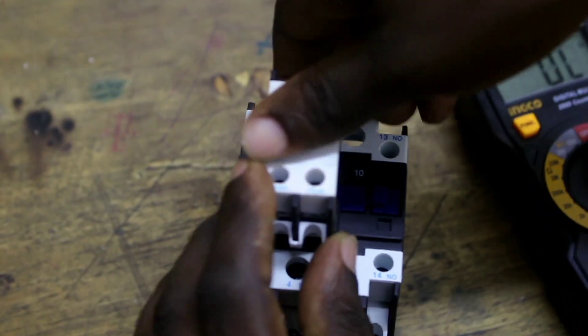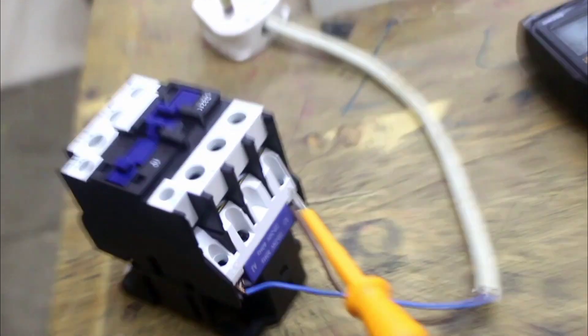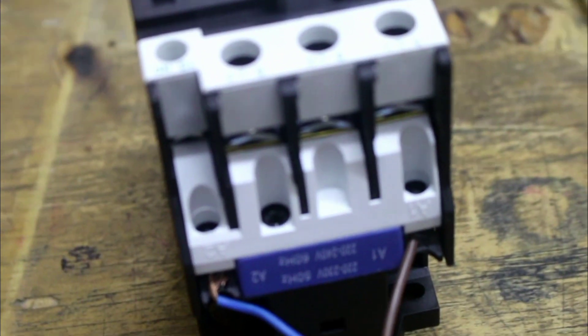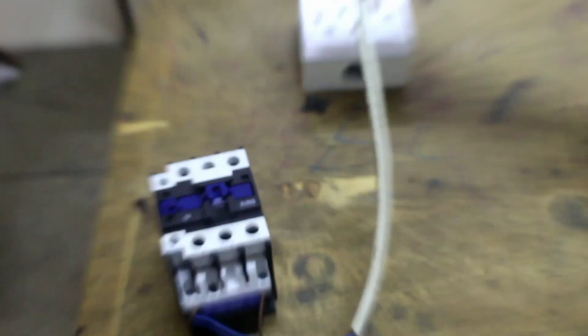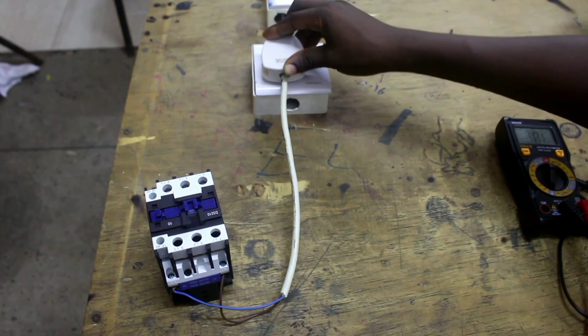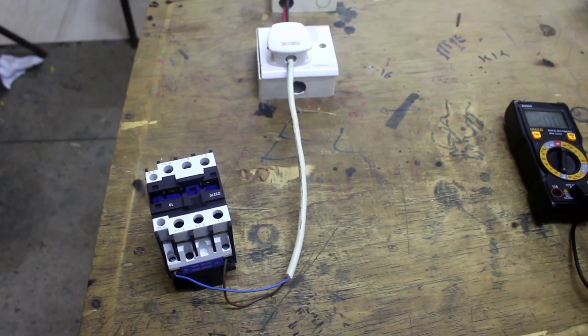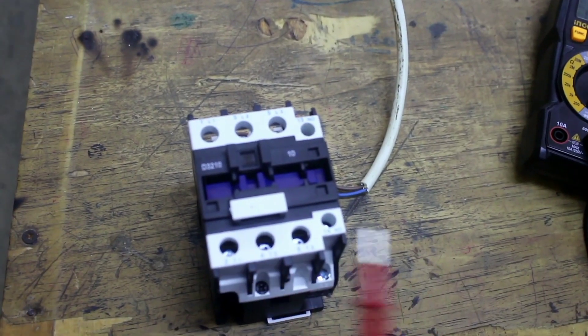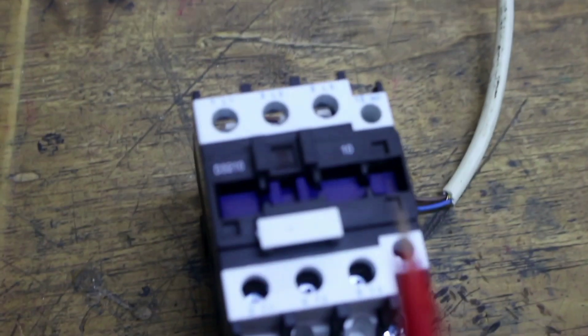Remove the auxiliary contact. Use a power cord to supply your electromagnetic contactor with power. Connect phase to A1 and neutral to A2 to energize the contactor by supplying the coil with power. Connect the adapter to power and switch on. You can see the contactor has been energized. When energized, all normally open terminals should now be closed, showing continuity.